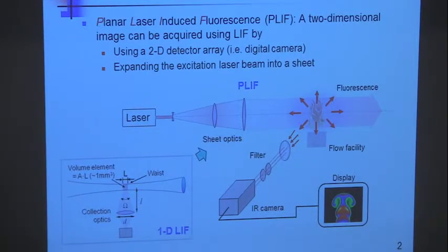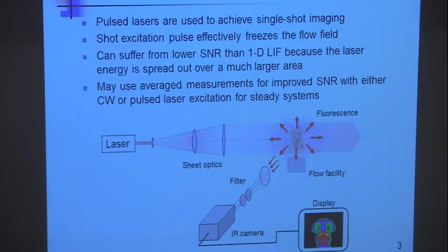In the case of usually the output image, the detectors are sensitive in the visible. So if the light is in the UV, you have to go through a stage in which you convert the UV photons into electrons, which then produce a visible image. So there's stages in these cameras to convert the wavelengths that you have into finally the false color display of the signal.